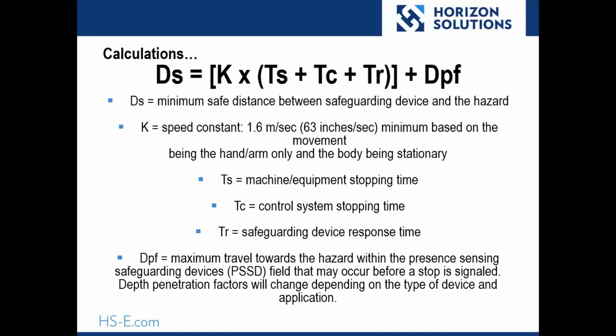DPF, or depth penetration factor, is the amount of penetration through the safeguarding device's sensing field that may occur before the stop issue is actually signaled.